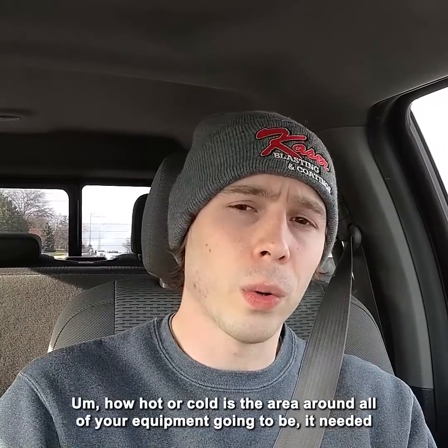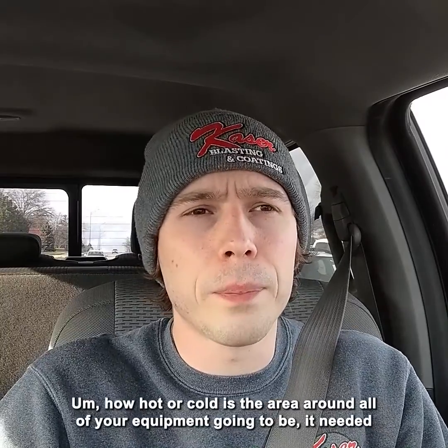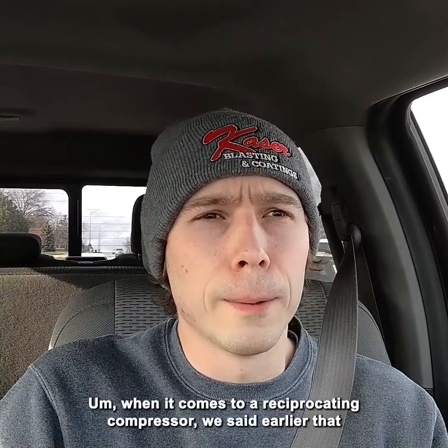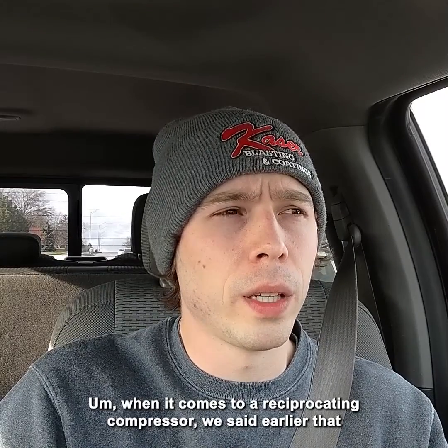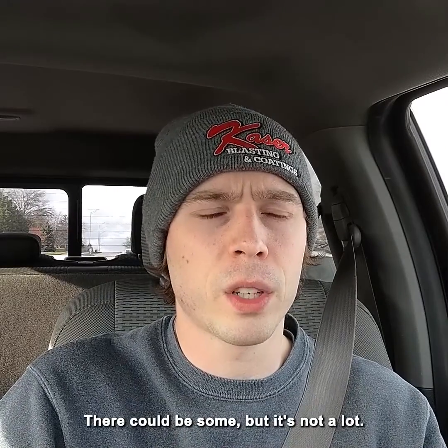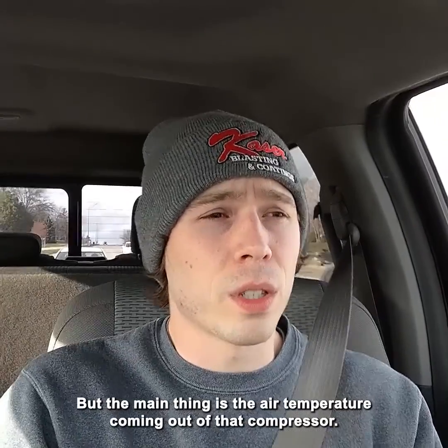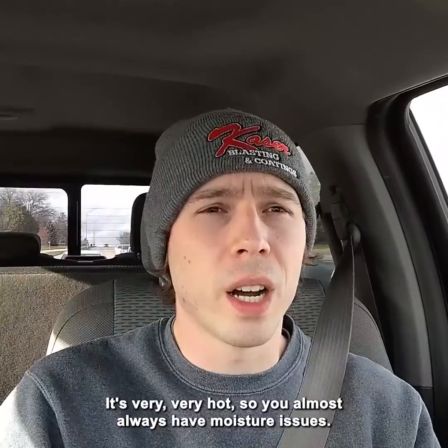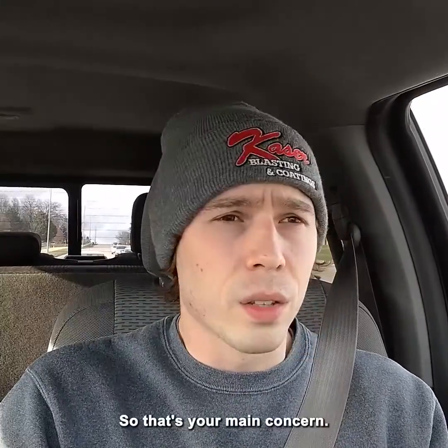How hot or cold is the area around all of your equipment going to be? And you need to take that all into consideration. When it comes to a reciprocating compressor, we said earlier that there's really not that much oil that we need to worry about. There could be some, but it's not a lot. But the main thing is the air temperature coming out of that compressor is very, very hot, so you almost always have moisture issues. So that's your main concern.